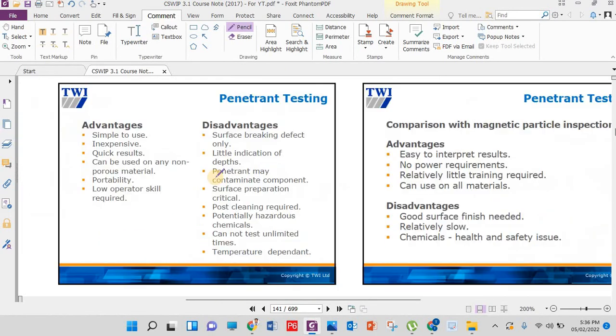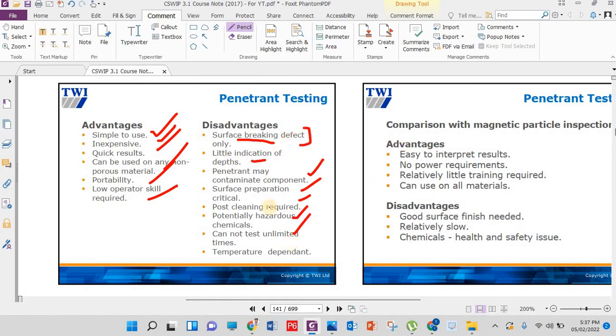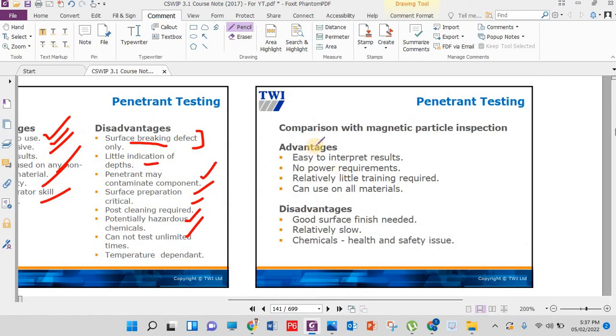Advantages of DPT: very simple, inexpensive, quick results, can be used on any material, portable, low operator skill required. Disadvantages: surface breaking defects only — this is the most important point, it is only for surface breaking defects. Little indication of depth — we can't estimate how deep the defect is. Penetrant may contaminate component, surface preparation and post-cleaning required, and hazardous chemicals involved.